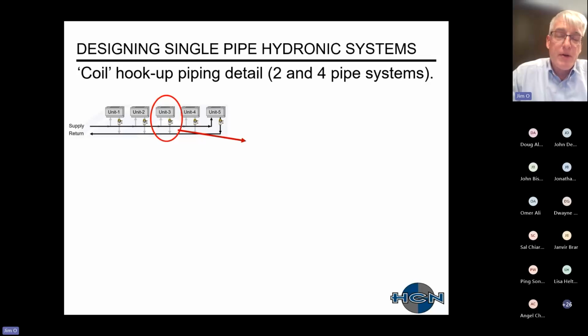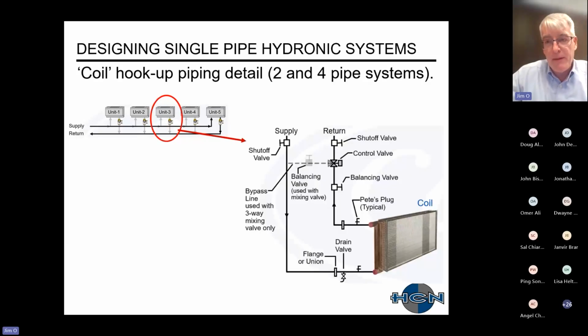Let's look at the typical piping hookups for a four pipe system. This is an old detail from a previous vendor that I worked at. This just shows a typical supply and return hookup, or branch piping, run out to the coil. Just going through it quickly, you have shutoff valves for isolation. You have a flange or a union at the coil if you have to remove it. There's Pete's plugs where you can hook up a thermometer or a pressure gauge, a balancing valve for balancing the water flow. There's a drain valve for draining the system if it's isolated for replacement.